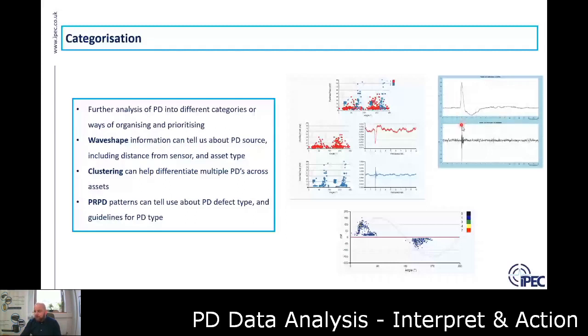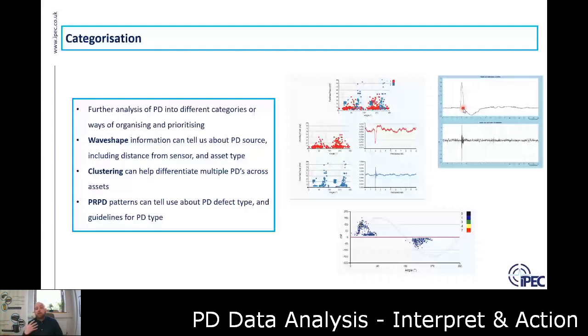On the right-hand side, there's an example. On the top, this is a PD coming from a few hundred meters down a cable; on the bottom, this is a PD coming from the switchgear next to the sensor. When a PD occurs, the frequency characteristics change as the signal propagates away from the source. A local switchgear PD remains a relatively high-frequency signal — a very fast pulse that attenuates quickly. A PD that's traveled along the cable loses its high-frequency components, and the lower-frequency components become more prominent, resulting in a much slower, lower-frequency PD waveform. So the individual wave shape gives us an indication of where the PD source may be relative to the sensor.